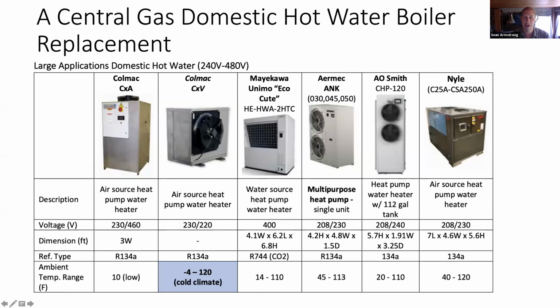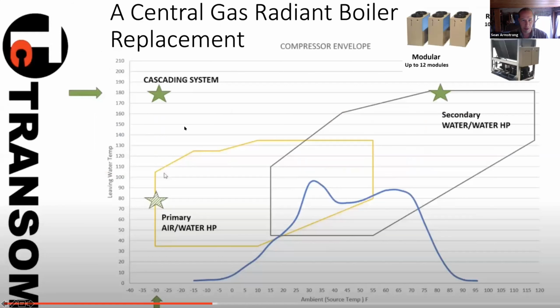You'd heat up water to say 100 degrees with this, and then put it into another Colmac heat pump water heater—not that one pictured, since that's air source, but it'd be water source. You can do negative 30 Fahrenheit with one heat pump. This shows the heating capacity package with the ambient outside air and the water temperatures you're trying to reach. It's called a cascading system.